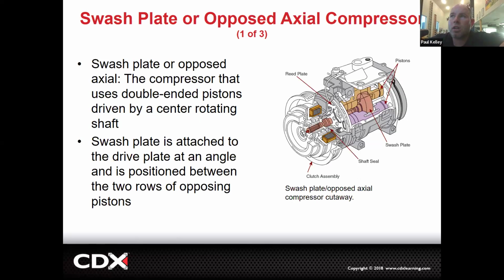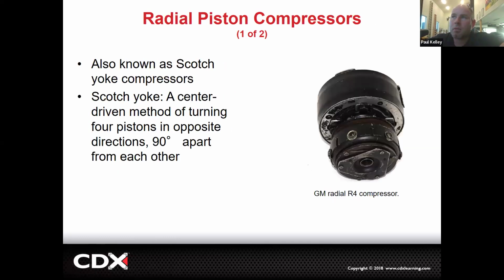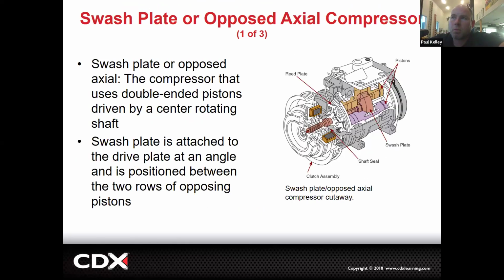So if you look at all these, there's something in common. There's pistons on pistons on pistons, right? And those pistons have little rings. And when the little Teflon rings get worn, they no longer make as much suction and they no longer move as much refrigerant. So you're going to have compressors that are not going to pull the low low enough and they're not going to push the high high enough. And the more miles and the more time, those little rings wear more and more. And next thing you know, your high is not as high as it should be. And your low is not as low as it should be, right?